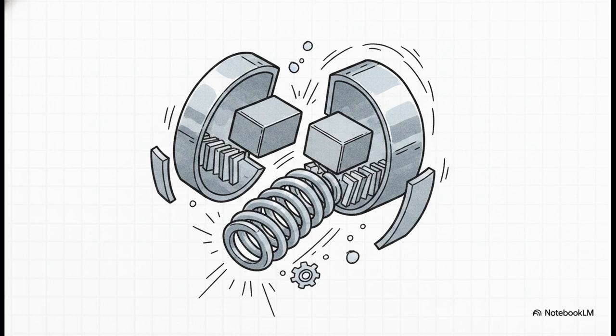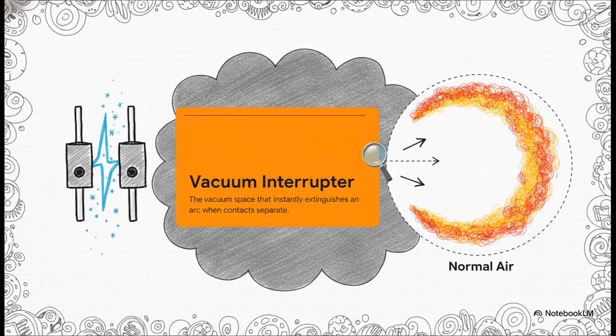But the absolute star of the show is part number 3, the vacuum interrupter. This is the absolute superpower zone of the VCB. When those highly energized contacts pull apart, the electricity desperately wants to keep flowing, right? So it creates an arc. In normal air, that arc would burn incredibly hot, ionizing the air to sustain itself.